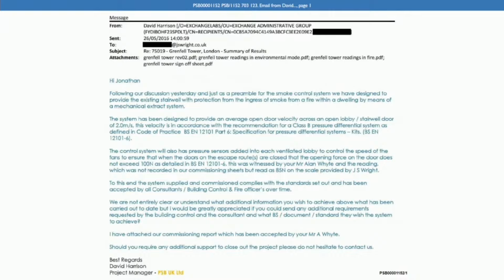And then in the third paragraph it says, the control system also has pressure sensors added into each ventilated lobby to control the speed of the fans to ensure that when the doors on the escape routes are closed, the opening force on the door does not exceed 100 newtons, as detailed in British Standard 12101 Part 6. This was witnessed by your Mr. Alan White, and the reading, which was not recorded in our commissioning sheets, but read as 85 newtons on the scale provided by J.S. Wright. Do you see that there? I do, yes.